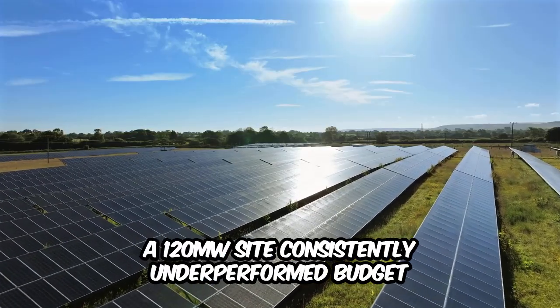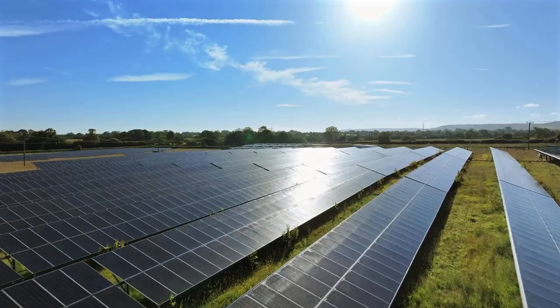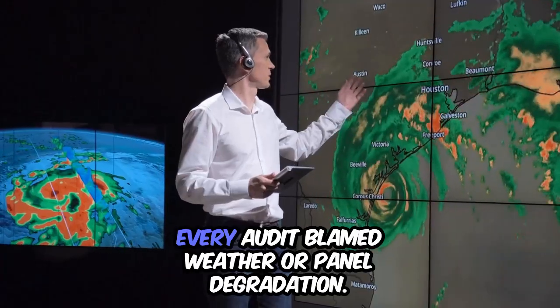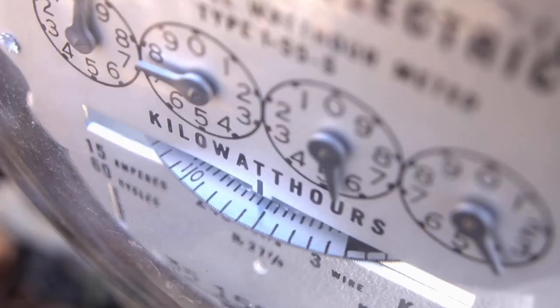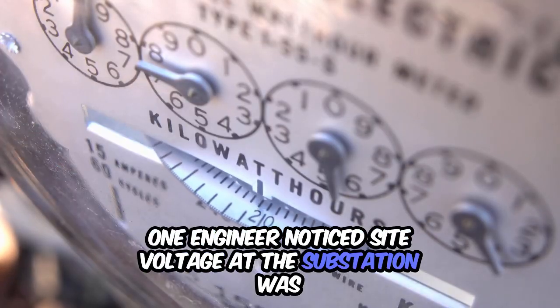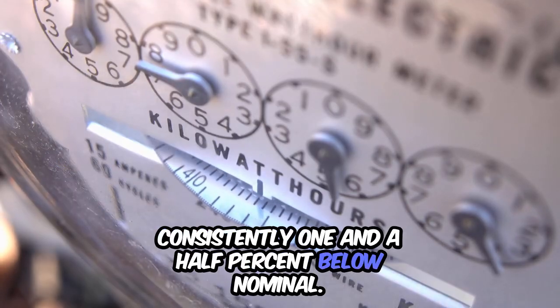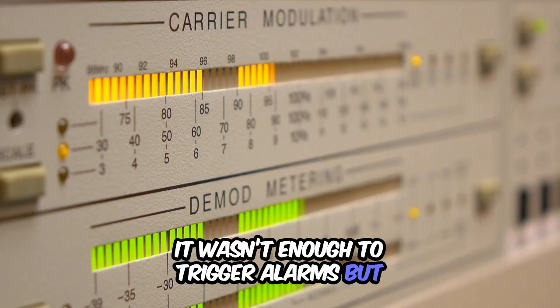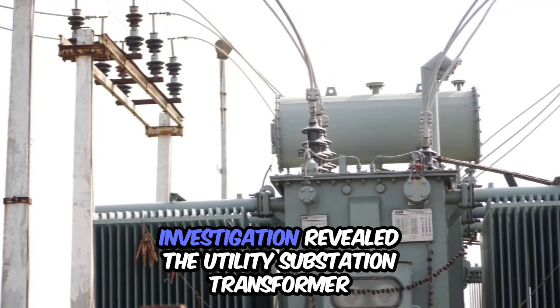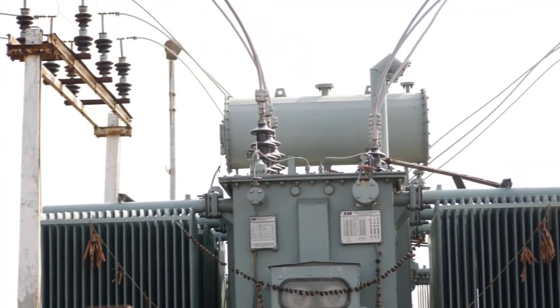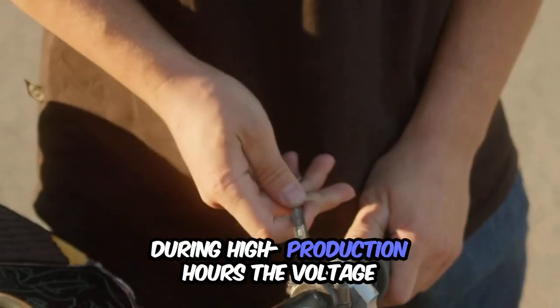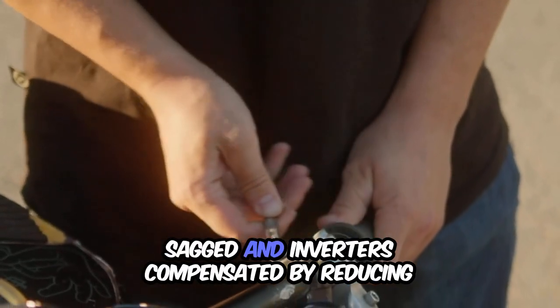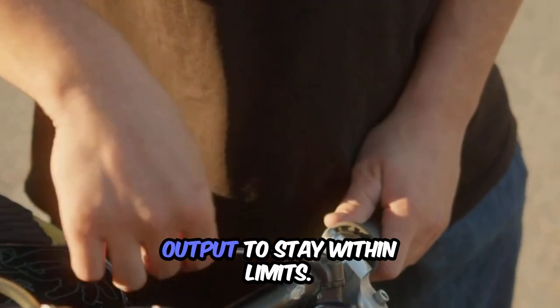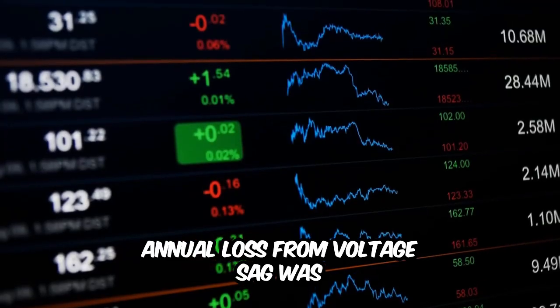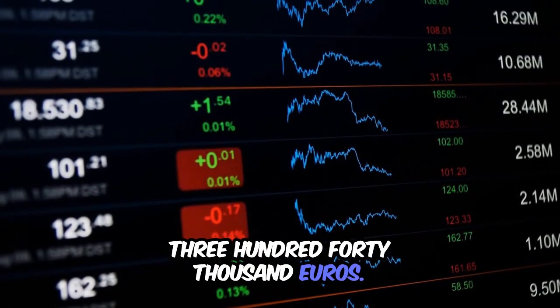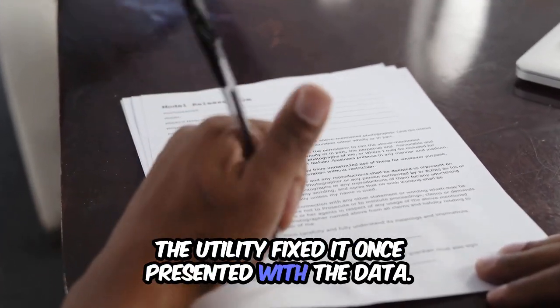A 120 MW site consistently underperformed budget by 4 to 5%. Every audit blamed weather or panel degradation. One engineer noticed site voltage at the substation was consistently 1.5% below nominal. It wasn't enough to trigger alarms, but it was enough to reduce output. Investigation revealed the utility substation transformer was undersized for peak load. During high production hours, the voltage sagged, and inverters compensated by reducing output to stay within limits. Annual loss from voltage sag was 340,000 euros. The utility fixed it once presented with the data.